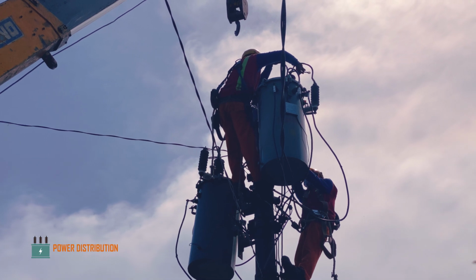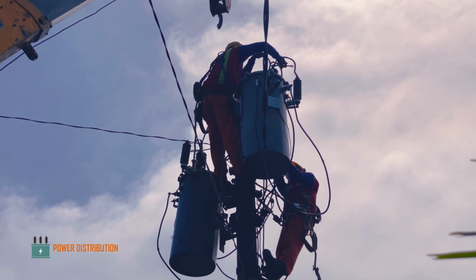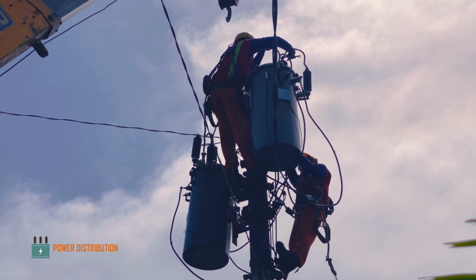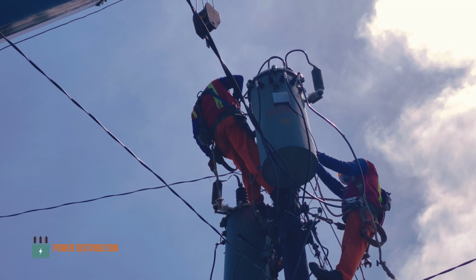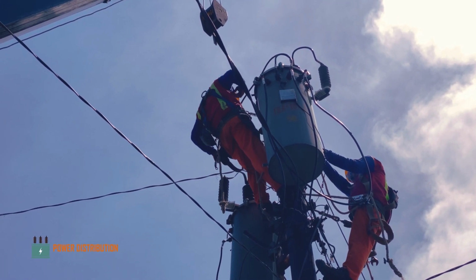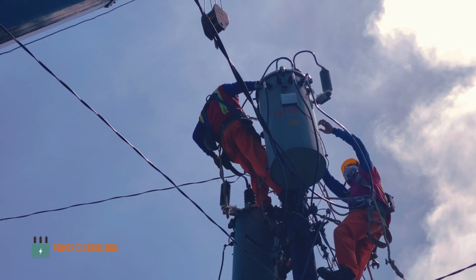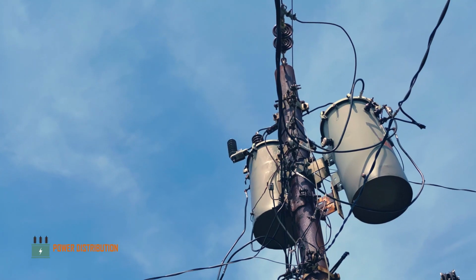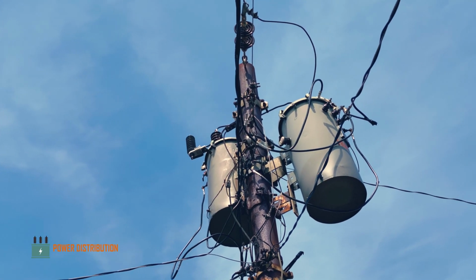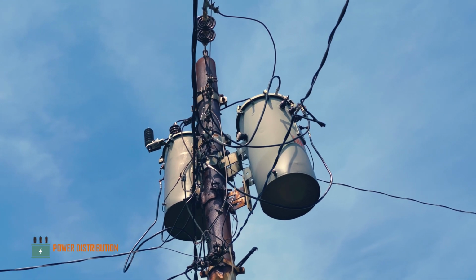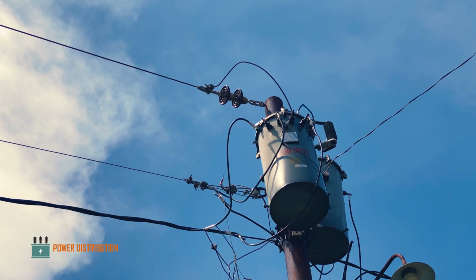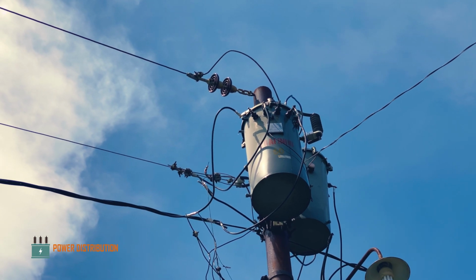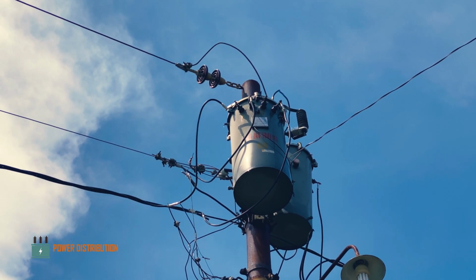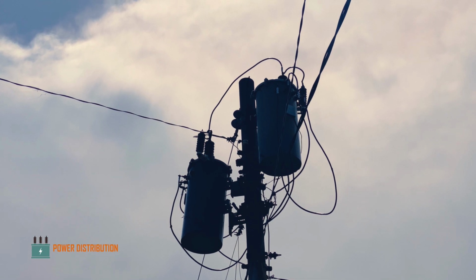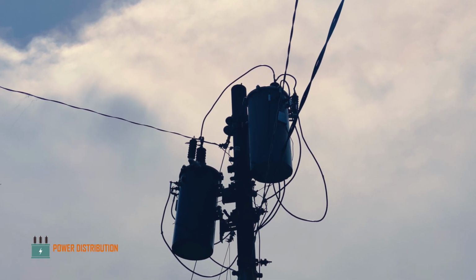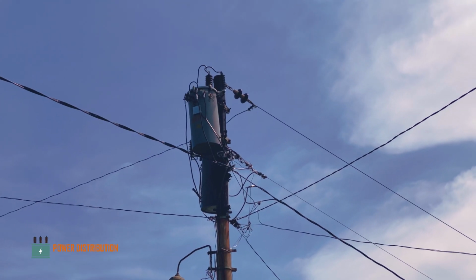And last but not least, the left crew installs the primary jumpers from the primary bushing and the surge arrestor to the single phase line. Now all the installation process has been completed and these two transformers are ready to be energized again. There you have it guys, the quick installation process of adding a new single phase transformer into the single phase line.